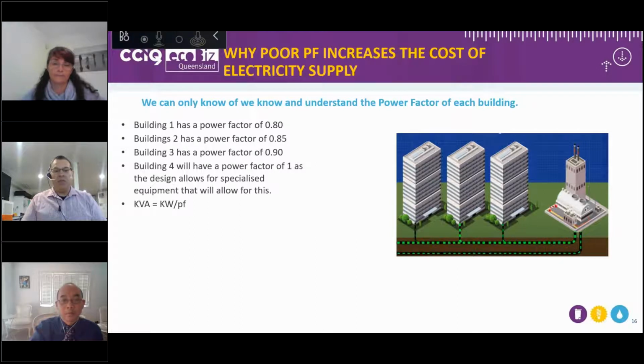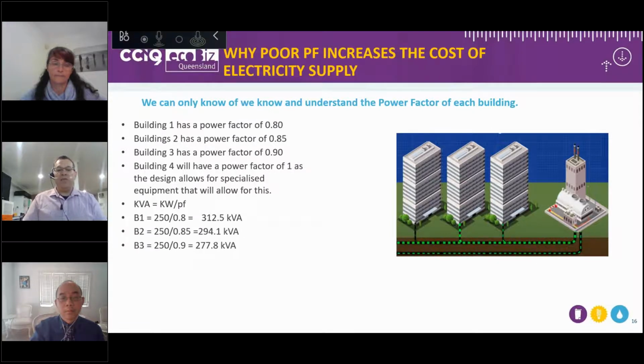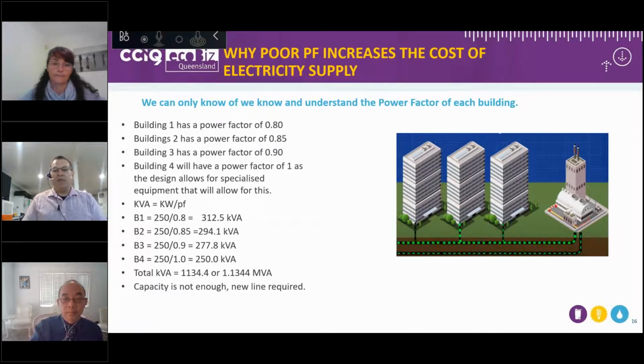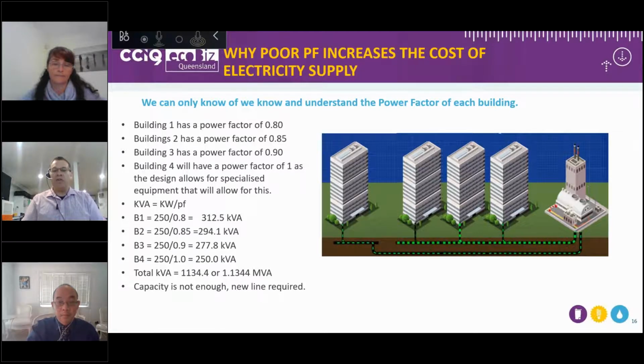Using our formulation, we know that our kVA equals our kilowatts divided by our power factor. So therefore, we get for the first building 312 odd kVA, then 294 and 277, and 250 for building 4, which gives us a total of about 1.13 MVA of load that the network line needs to carry. Capacity is not enough, so a new line is required. There are therefore new infrastructure costs for the network. Of course, the cost of that infrastructure will be borne by all customers.